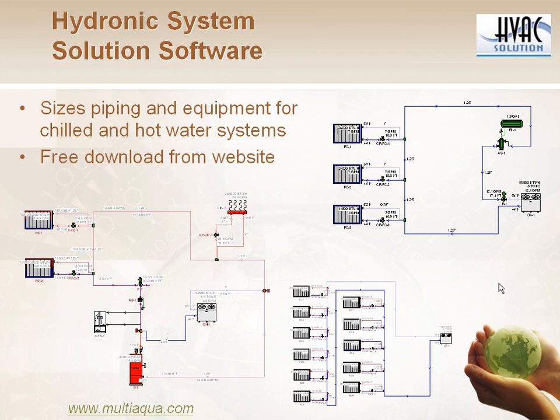It's pretty cool too, because you can do professional-looking drawings, lay out all the coils or the radiant floor, or the swimming pool, or whatever it is you're trying to heat, show the boiler, show the piping. The software not only will make it all look good for you and show you all the various loads on there, but it'll also size the pumps for you and size the piping for you. So it'll tell you, oh, you need 2-inch pipe on this segment in order to make that flow happen, etc. Like any other software, garbage in, garbage out, so you still got to know what you're doing, but at least it kind of beats doing everything by hand, if you will.